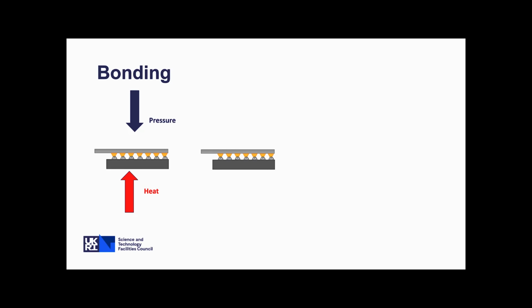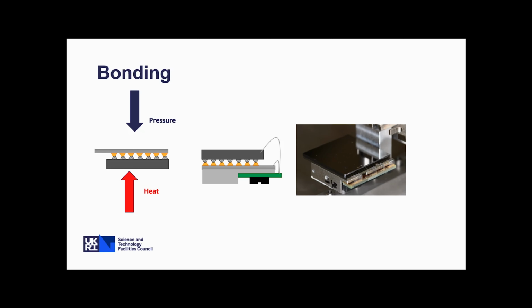Once that's cured, we take it out of the machine, we flip it over, and then we connect our base plate to it, an aluminium base plate, and there's a readout PCB connected on the bottom. We wire bond to the ASIC, and we apply a wire bond to the top to apply the bias to the top of the detector, at 500 volts, which gives us the electric field. Then it gives us our finished module, which plugs into our readout electronics. So it's a modular design that you can put into the electronics, and you can swap them in and out if you wanted to. You can also see that it's a three-side buttable design as well.